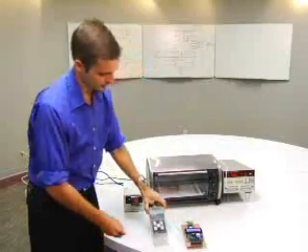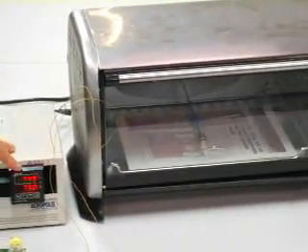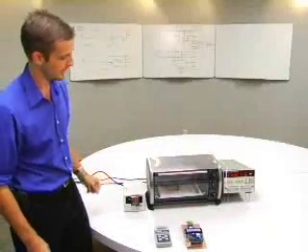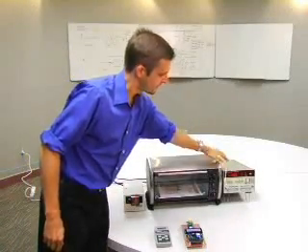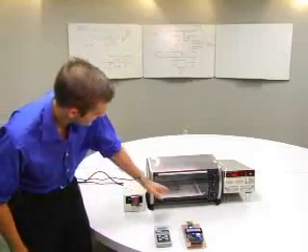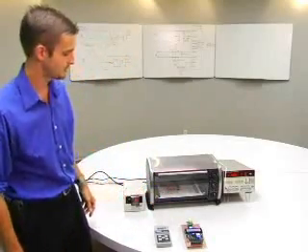We've also got a commercial thermocouple meter to compare it to. We've also got a specially modified toaster oven with a PID controller that gives about 0.1 degree centigrade stability to make it a little more useful for calibration purposes, and a quartz resonant thermometer to compare both of these against. And inside the oven we've got the quartz probe and two thermocouples all in close proximity.